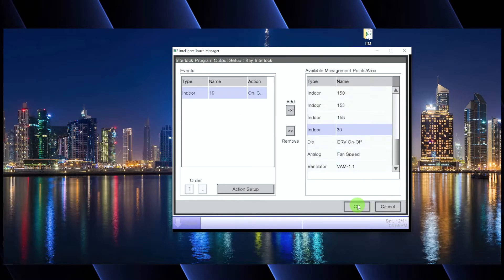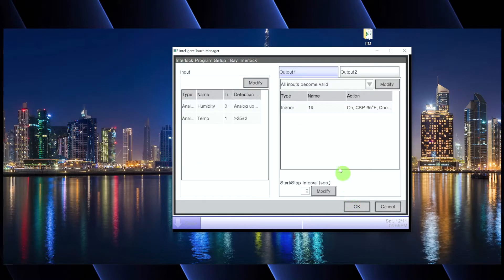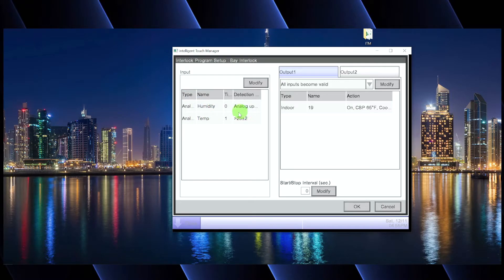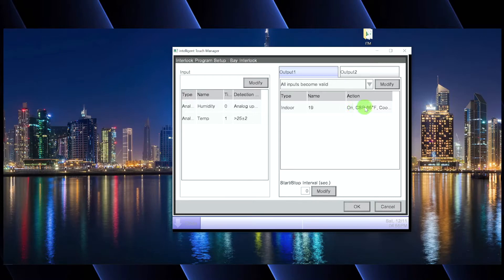So we're saying: if the humidity hits the upper limit of 70% and the temperature gets above 25 degrees — in the real world this would be set to something like 80 — if both of those inputs become valid true statements, then we tell indoor unit 19 to turn on, go to cooling mode, crank down to 65, and put the fan speed on high. This is kind of an emergency response: the room is getting way too hot and too humid. That's output one.